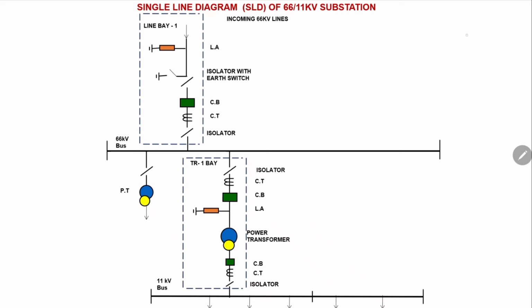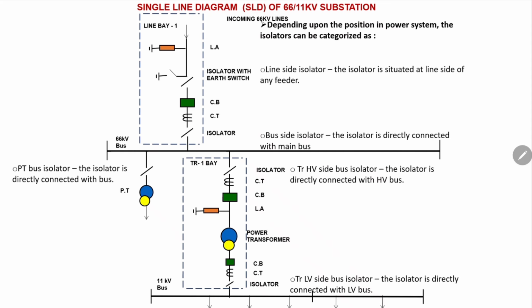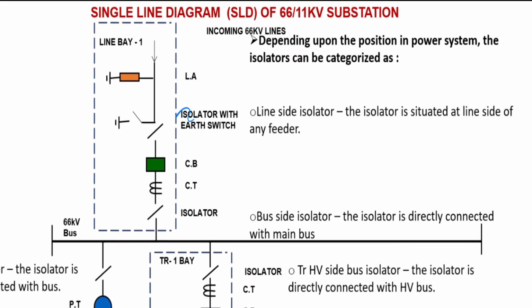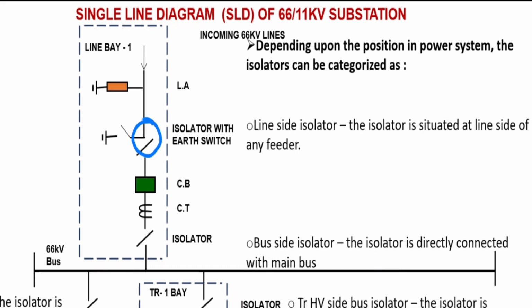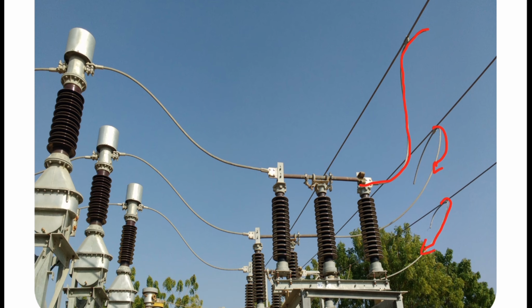here. Let us focus on the line bay SLD. Depending upon the position of the isolator, the nomenclature followed is that isolators connected on the line side are called line isolators. Isolators connected close to the bus side are called bus isolators. Let us take a practical overview. As shown here, this isolator is directly connected to the main bus, so this isolator is called a bus isolator.